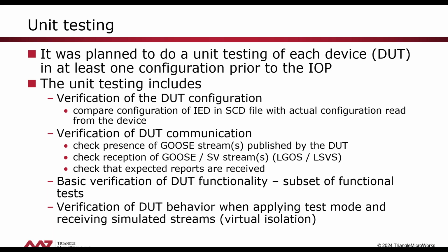The unit testing included a verification of the configuration, comparing the configuration in the device against what was expected from the SCD file, to be sure that the right configuration was loaded into the device. Verification of the communication, like presence of GOOSE streams, check the reception of GOOSE streams in the LGOS, LSVS logical nodes, and also check that the reports are published and sent.